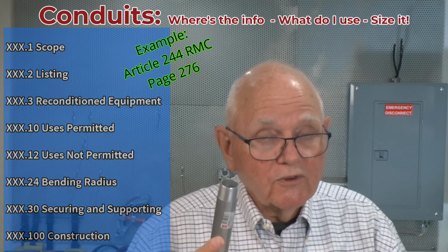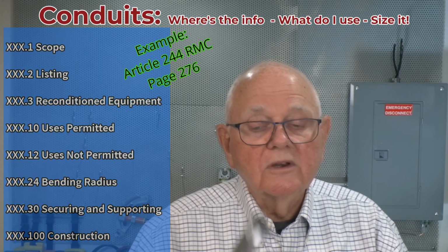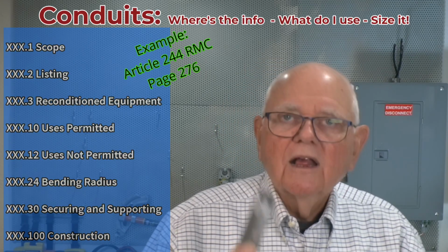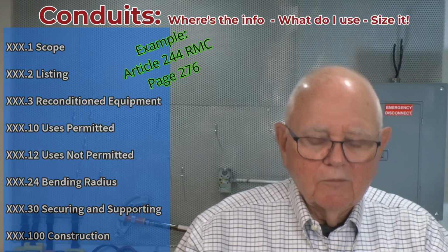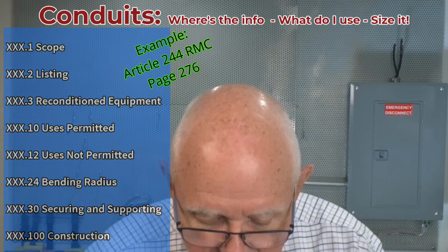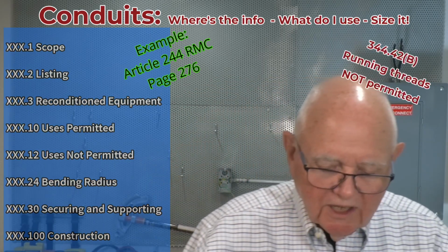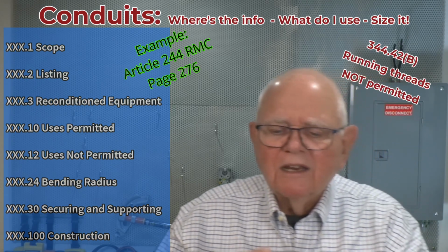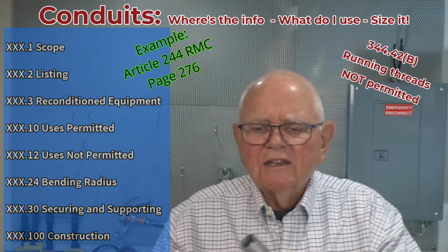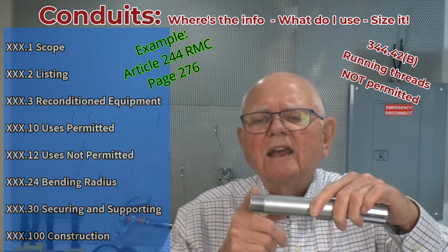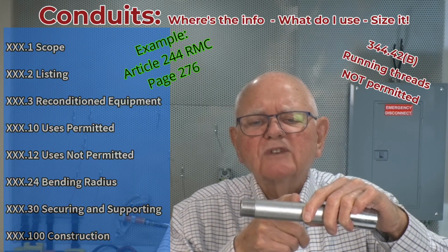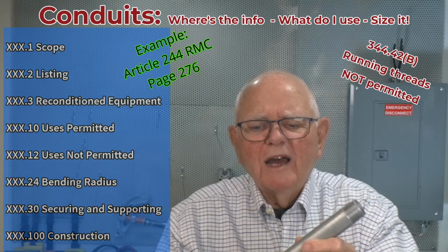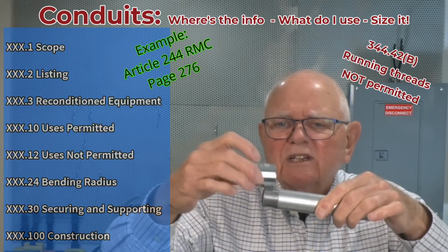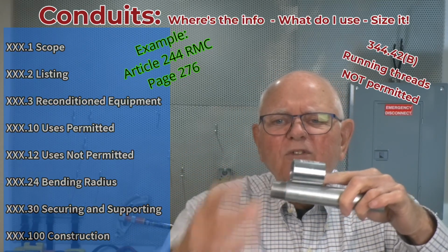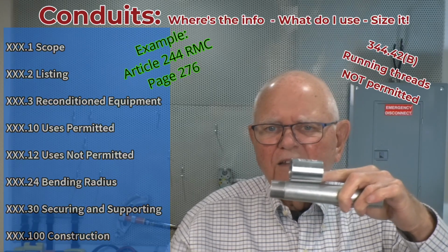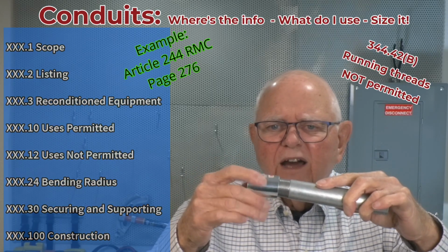So I want to use the proper tool in order to ream out my conduit. When it comes to threading my conduit, I want to follow my instructions. It talks in here about running threads, 344.42, and it talks about running threads are NOT permitted. We said these threads were tapered, right? And so if I were to go ahead and cut threads, I don't know, 2 or 3 inches up here on this nipple, my goodness, I could take this guy and I could just screw it all the way on there, huh? I haven't made up anything very tight, and that'd be ridiculous. I don't want that. So follow your instructions.